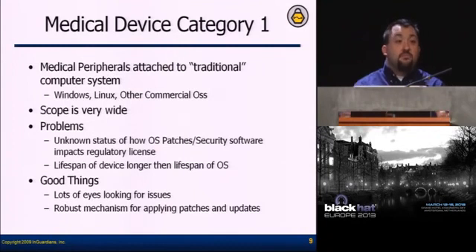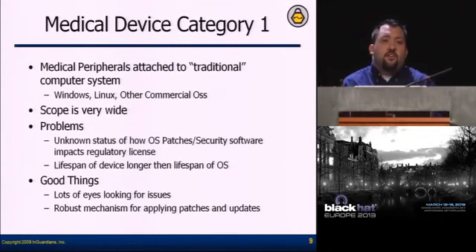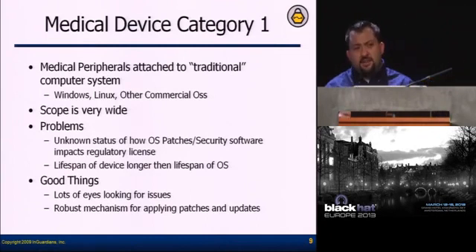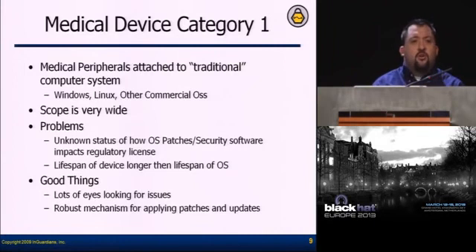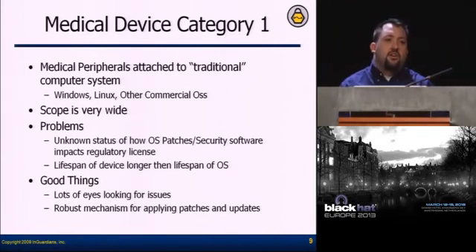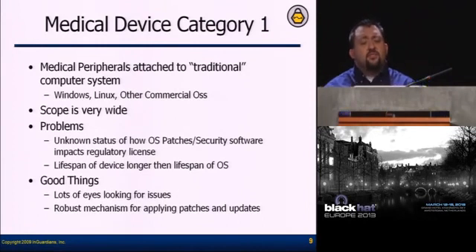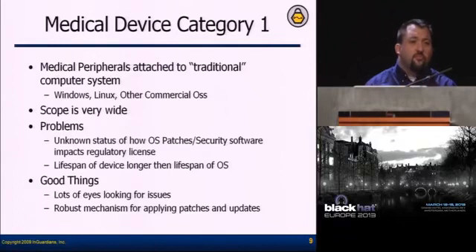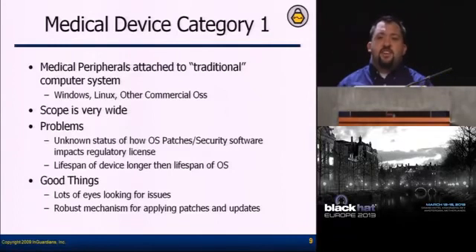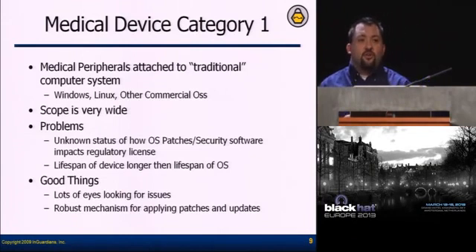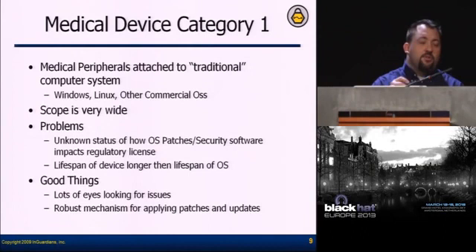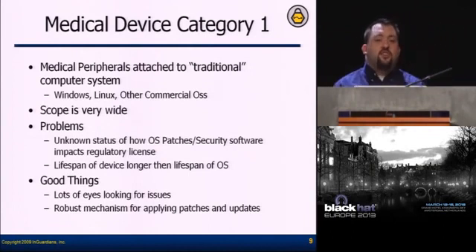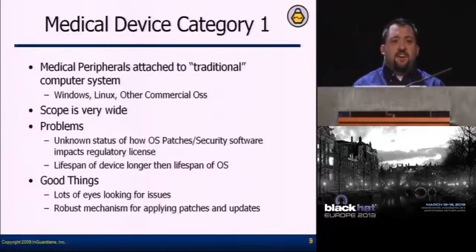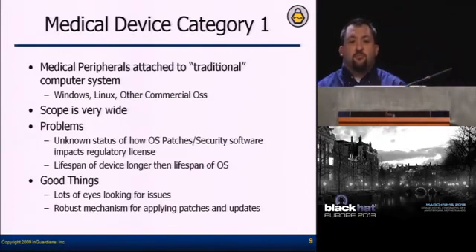And that's why hospitals are very hesitant and vendors are very hesitant to say, oh yeah, go ahead and patch it. Go ahead and change the operating system. Go ahead and apply this patch or apply this security product and the device will work fine. They're not certain of that, so they don't do it. Also a problem is the lifespan of these devices is often longer than the lifespan of the operating system, right? You buy an MRI machine, you expect to keep that machine 10, 15 years. Operating systems don't last that long. So if you built your MRI machine based on Windows 3.1.1 and you expected it to last 15 years, when you get to year 5 and that's not supported anymore as an operating system, you're in significant trouble.